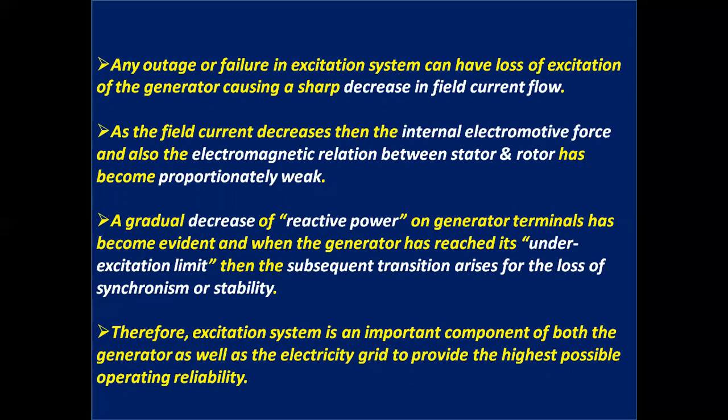A gradual decrease of reactive power on generator terminals becomes evident, and when the generator has reached its under excitation limit, then the subsequent transition arises for the loss of synchronism or stability. Therefore, the excitation system is an important component of both the generator as well as the electricity grid to provide the highest possible operating reliability.